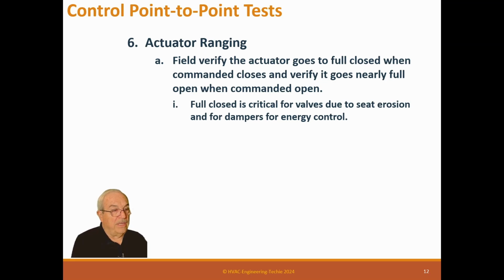The way you do that is the adjustment linkage on the top of the valve actually adjusts how far down that stem goes to close off the valve. So you need to make sure that's adjusted correctly so it goes full close. If it then limits the stroke and it only goes 99% open, you're good, not a big problem. Even if it's a globe valve, you will still get full flow, but you need to be full closed for sure.